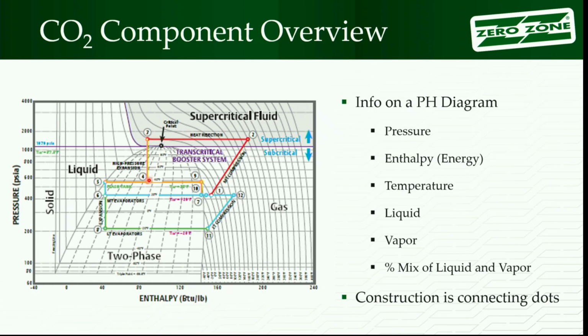And when we go through an expansion device, it comes out of the condenser and it doesn't change energy anymore. All that energy exchange happened in the condenser or the gas cooler. It's just strictly a pressure change. When I drop down, that pressure change, where it hits my line, which is the flash tank, when I get to 0.4, that tells me how much gas and how much liquid I have. So we're going to be watching, where does that point move? Is a point moving to the left as the operating conditions change, or is the point going to move to the right? And if you're doing flash gas, does it have any refrigerating value in the system? Not really. It just goes around and around.